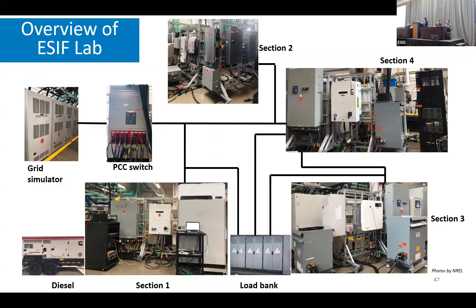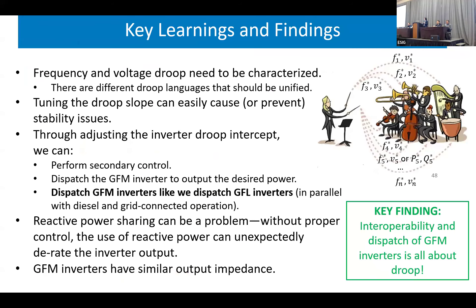This picture shows you the lab setup. As of today, we have tested all individual units and completed all section tests with a few inverters packed together. Now we enter the final phase to test them all together. We have already seen oscillations between sections, which is a very interesting phenomenon we are going to study further.